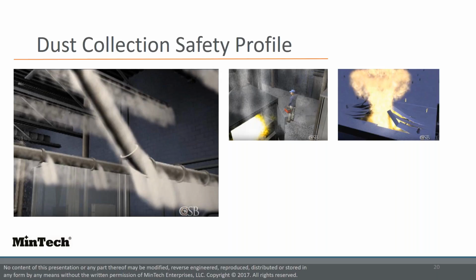As combustible dust awareness has increased, dust collector technology has also improved a great deal. New dust collector designs include explosion mitigation devices that help control the direction of the energy away from people and property. However, existing dust collectors still present a hazard, and it's challenging and often impossible to retrofit existing dust collector systems with these new explosion mitigation devices.